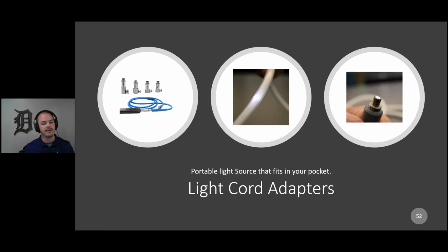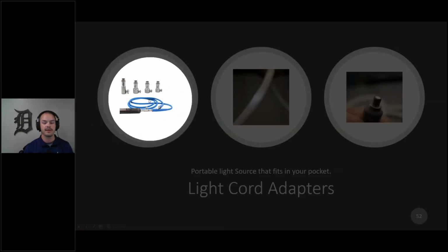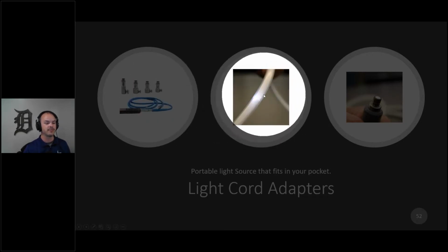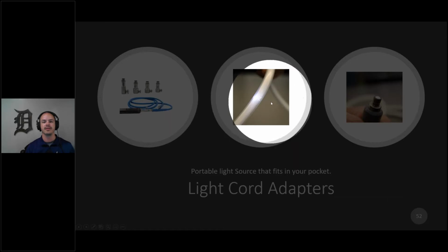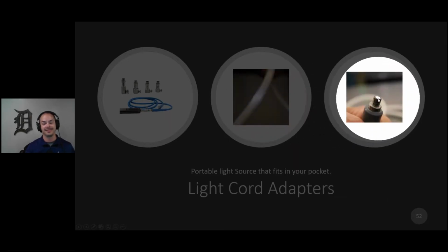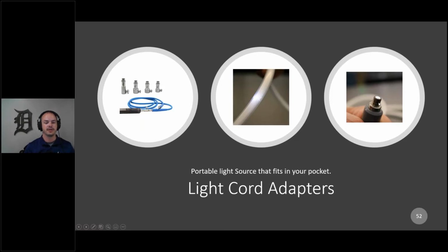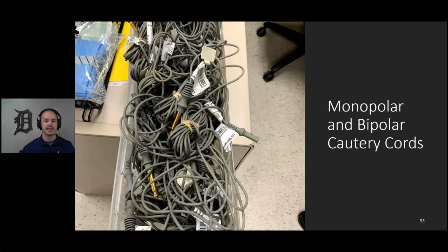This slide shows how a portable light cord adapter and a light source can help you do a quick quality check on your light cable. See that light popping out of the side of the cable? That's what we don't want to see—it shows broken fibers in the cable, with light escaping instead of reaching the end where the pointer is. So do a quick quality check with something simple like this to make sure the cord is intact before sending it to the operating room.